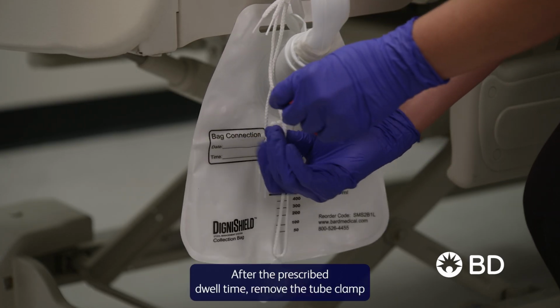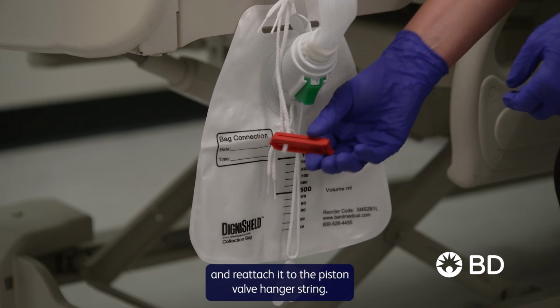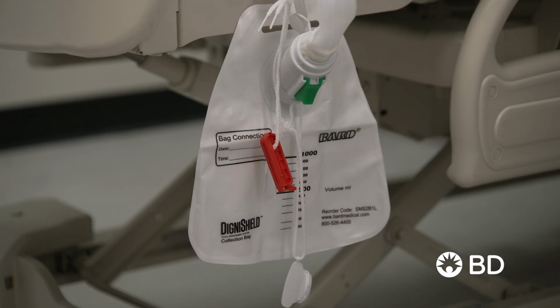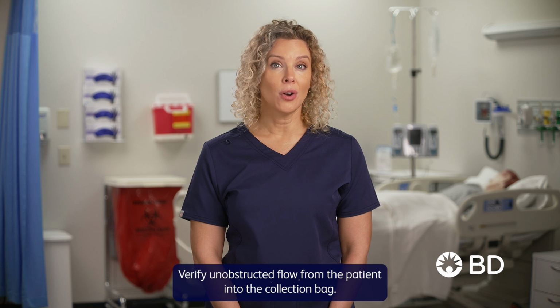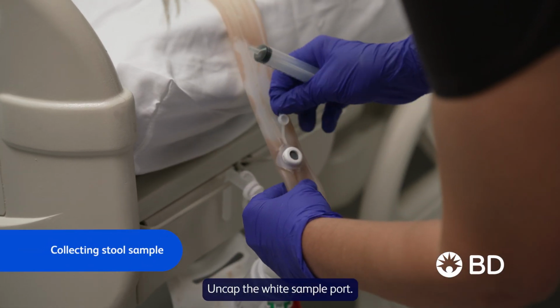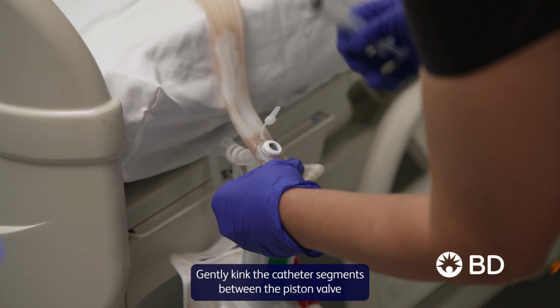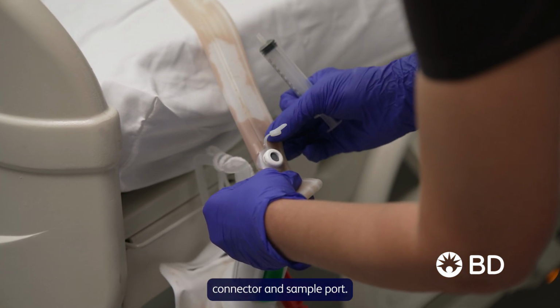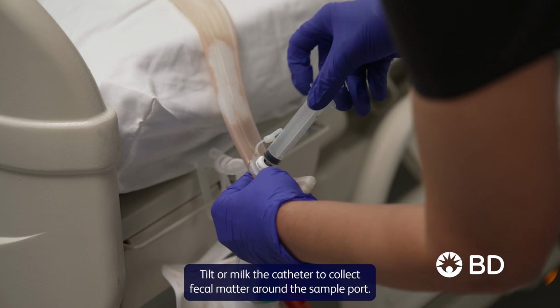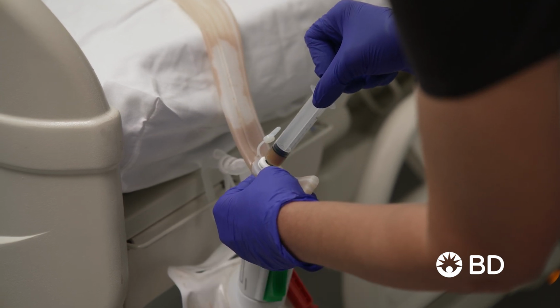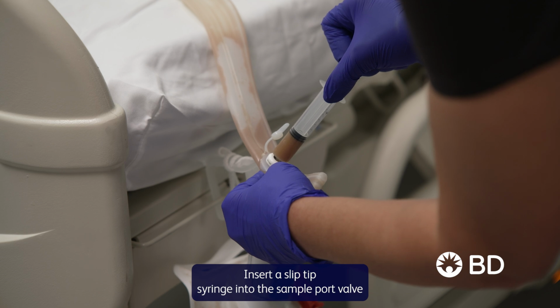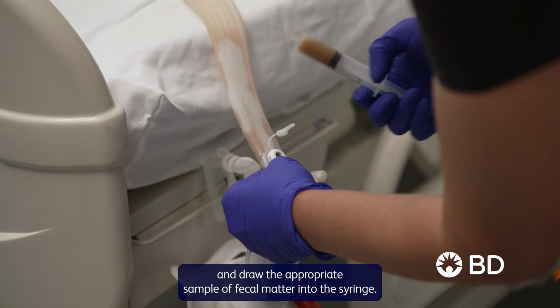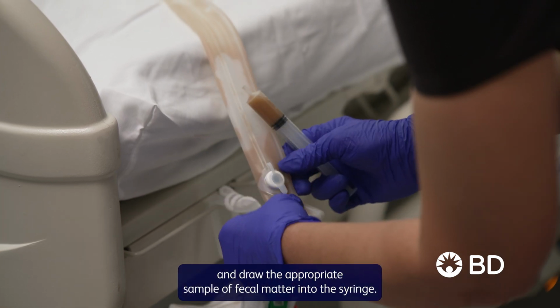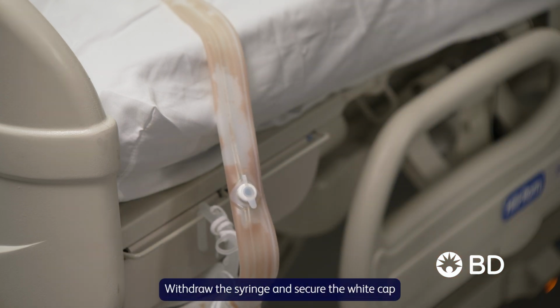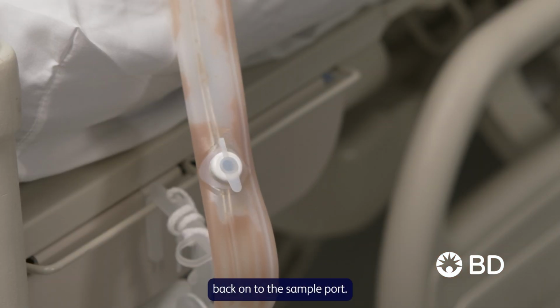After the prescribed dwell time, remove the tube clamp and reattach it to the piston valve hanger string. Verify unobstructed flow from the patient into the collection bag. Uncap the white sample port. Gently kink the catheter segments between the piston valve connector and sample port. Tilt or milk the catheter to collect fecal matter around the sample port. Insert a slip-tip syringe into the sample port valve and draw the appropriate sample of fecal matter into the syringe. Withdraw the syringe and secure the white cap back onto the sample port.